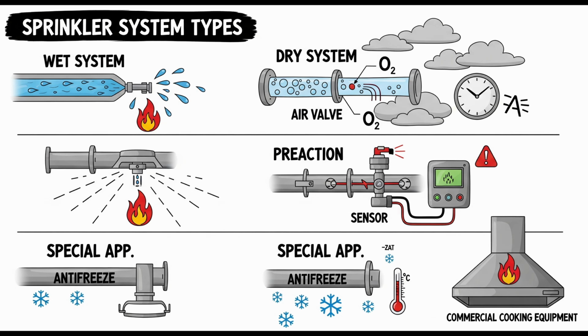Where are the sprinklers or nozzles located within the exhaust ducts themselves? The general rule is one sprinkler or nozzle is required at the top of each vertical riser in the ductwork and also at the midpoint of each significant offset change in direction in the duct. Protecting the high points and turns where grease might accumulate or flow could be restricted. Exactly. However, there are exceptions. Sprinklers aren't needed in vertical risers located outside the building if that riser doesn't expose any combustible building materials, or if the horizontal distance inside the building between the hood outlet and the start of the vertical riser is at least 25 feet, allowing grease to potentially cool or deposit before the riser.